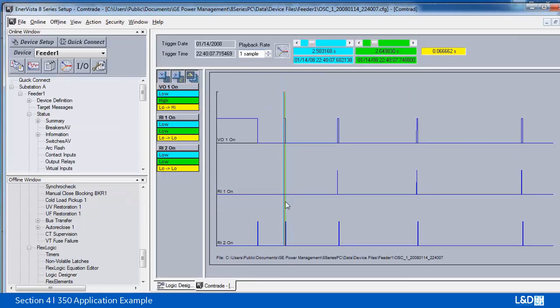Okay, so on the 850 side, we can see the remote input 1 from logic element 1, then remote input 2 from logic element 2. So we can see that the 4 shots of auto reclose on the 350 is reflected on the 850 side. And that concludes the demo of the auto reclose.